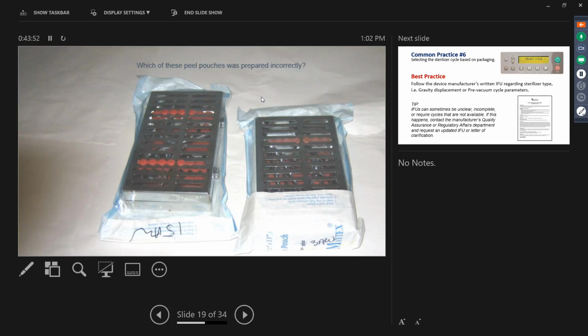You do know when the FDA clears a sterilization pouch with a self-seal, that when you seal it over, it has to catch 50% paper, 50% plastic, else the seal is not going to have integrity. Now there's some wiggle room - sometimes it's 60-40, sometimes it's 65-35. There's a little bit of wiggle room, but there's no wiggle room on this.